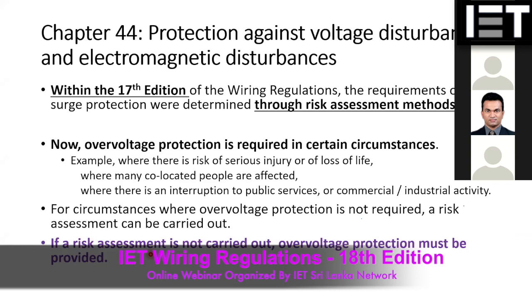Now people are getting more and more new problems, and most of our electrical equipment is highly vulnerable to voltage disturbances. Because of that you have to have a certain type of overvoltage protection as well. So the new requirement is introduced as chapter 44, on voltage disturbances as well as electromagnetic disturbances. You have to assess the risk, and then depending on the risk assessment, you have to propose overvoltage protection for the building.